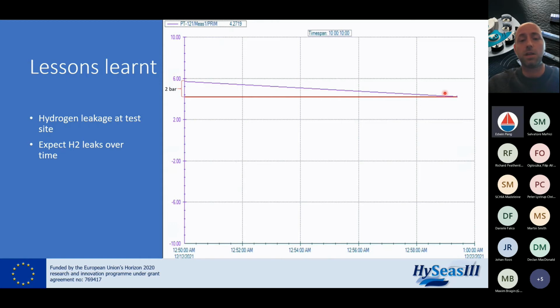And it's also outside the ignition range of the hydrogen, but it's an observation made over time, and it's also a preferred way of showing leaks that you may have in your system, even really small ones: to observe over time and have proper trending and proper actions to limit it. As I said, this was over 10 days just before Christmas, so there was no one on site. This was an observation after. For this system, we have 200 bars on the main canisters, and with pressure reduction there will be leakage through the reduction valves. They all have specified leakage rates, so it's actually to be expected. And hydrogen molecules are quite small, so it finds a way.